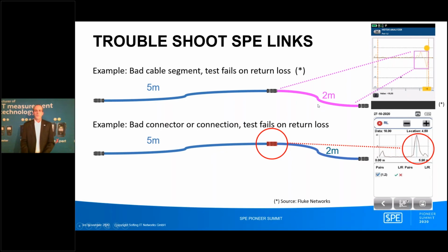Another example, from our Wire Xpert tester, shows a 5 meter good segment and a 2 meter good segment, but the connection between them is bad. Either it's poorly terminated, or the connector isn't rated for that performance, or something else. You see a small peak for the first connector, a small peak for the last connector, and a huge peak for the bad connection.